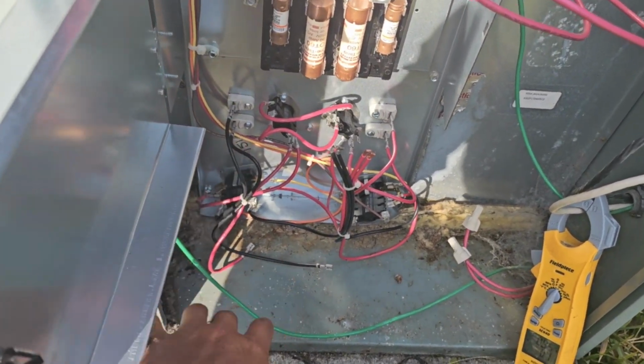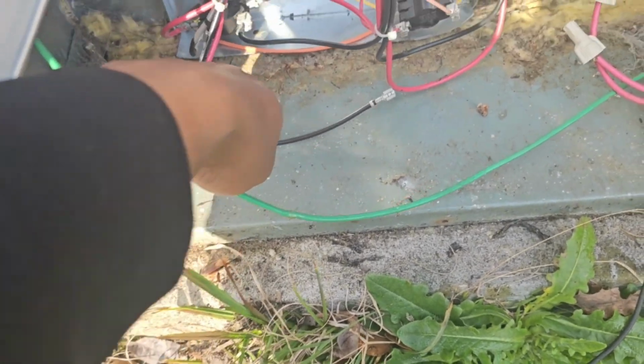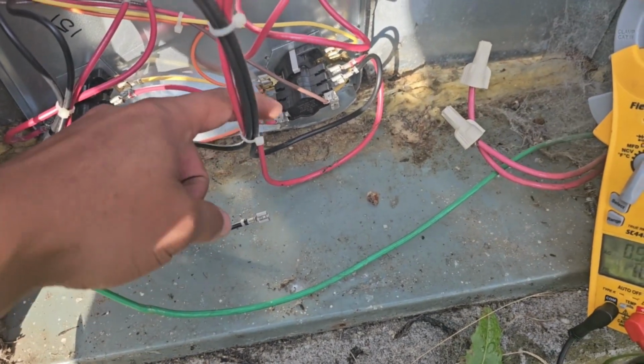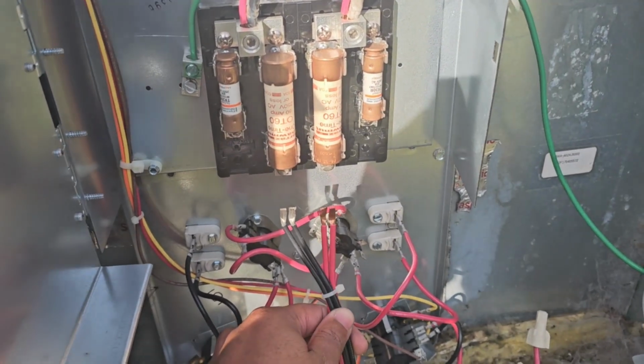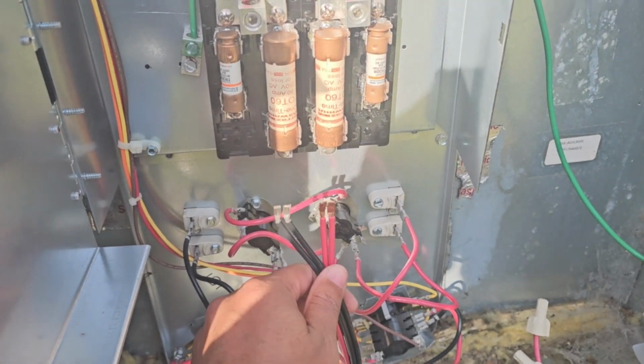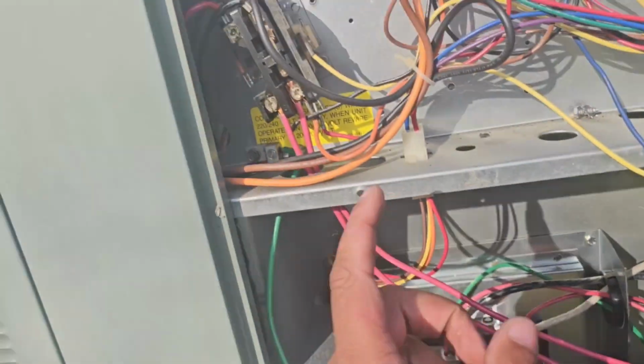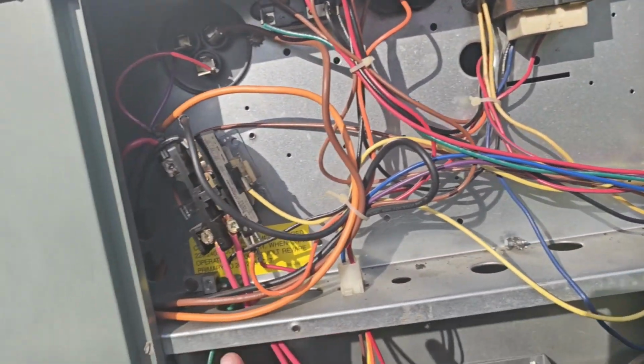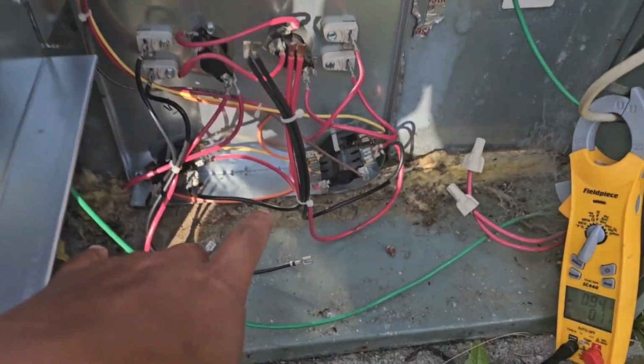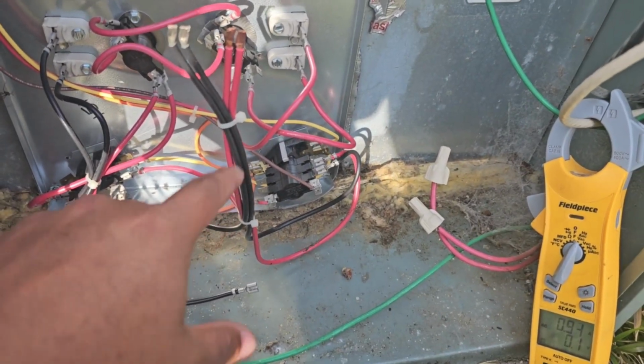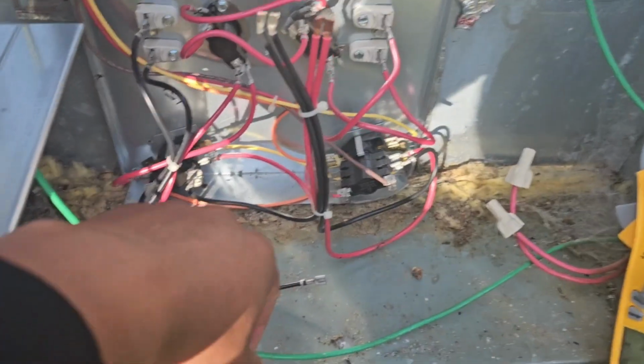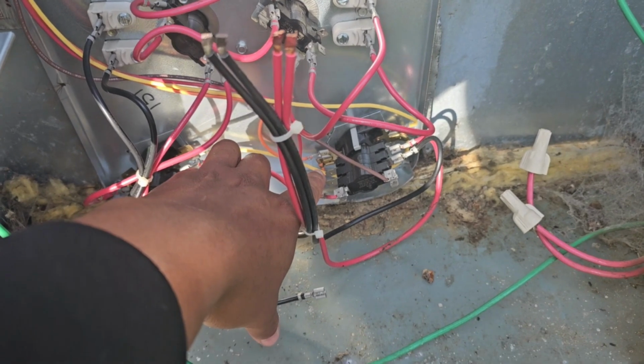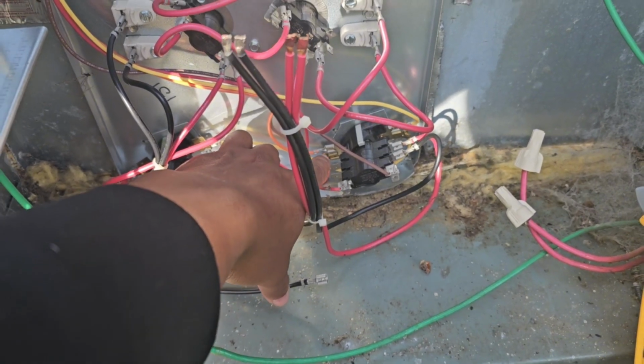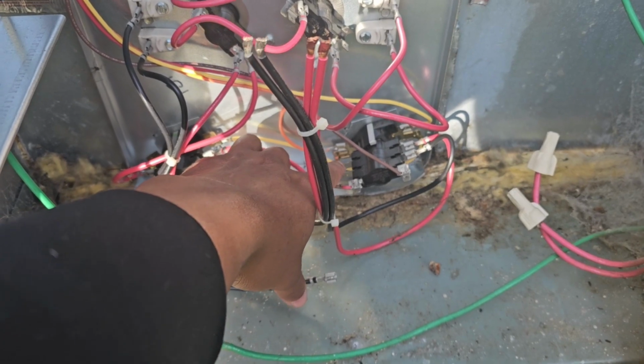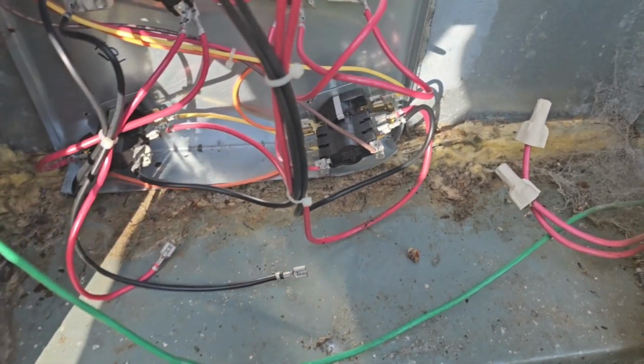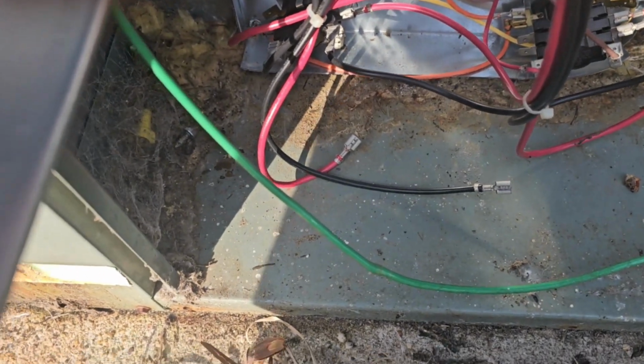So what I'm doing now is I've got the two wires I was testing on one side of the sequencer removed. I've got all high voltage power removed from the heat strip kit, but I still have power going to the transformer to control the low voltage, so my sequencer can still get energized. I want to see if something is going wrong on this end, where somehow these wires are becoming the same leg of power instead of separate. I think that's the next best place to look.